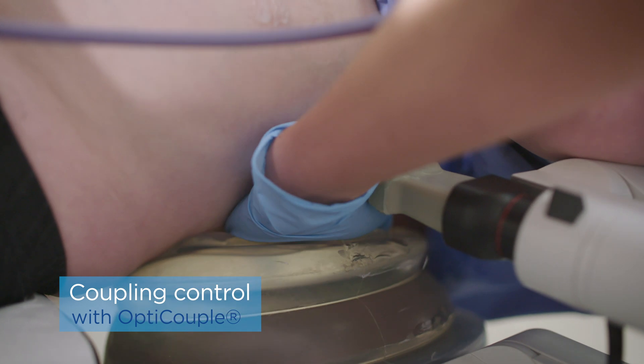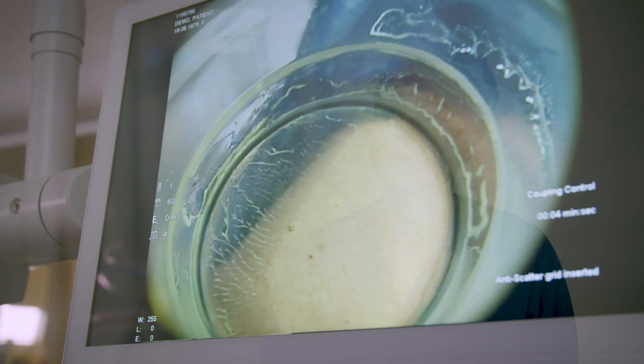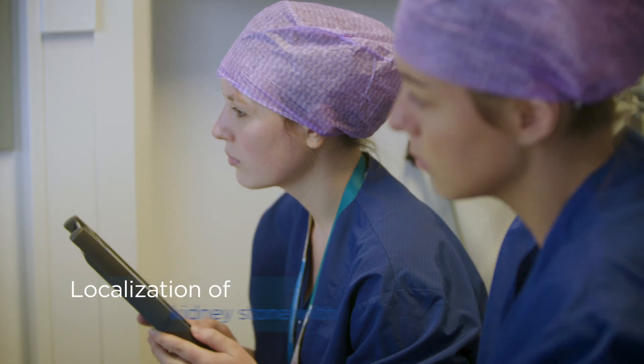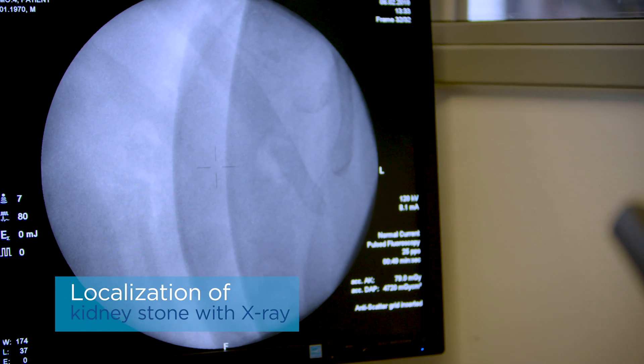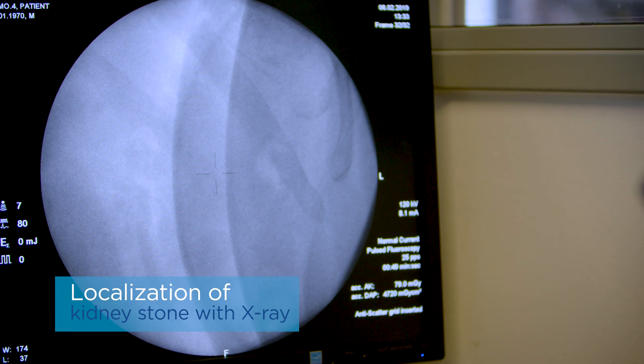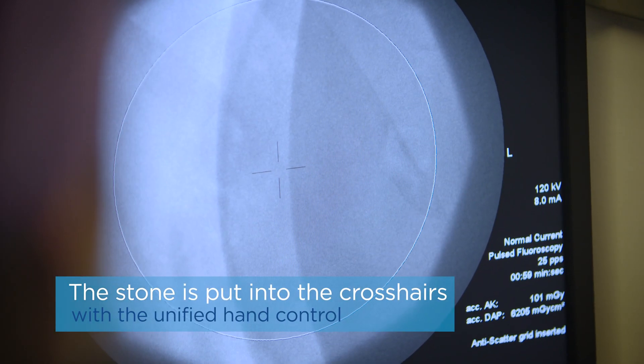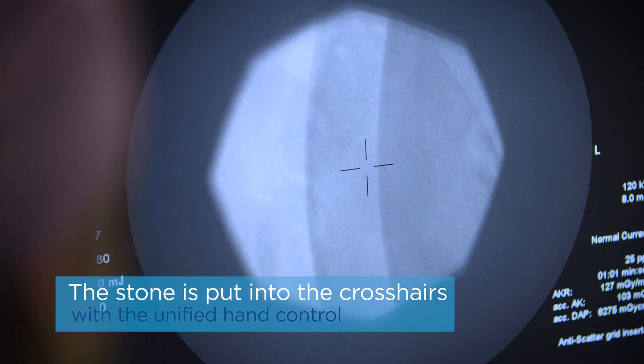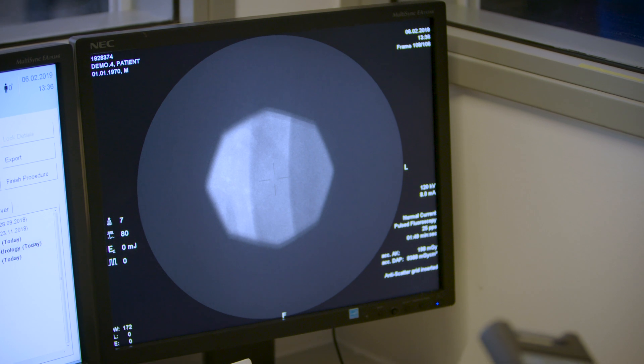The Delta III has an OptiCouple function, which enables us to view the connection between the balloon and the patient to make sure there aren't any air bubbles in between the balloon and the patient. Therefore we need to administer less shockwaves and also less energy per shockwave to reach an optimal treatment, because there are for sure no air bubbles that can stop the energy from being transferred from the balloon to the body of the patient.